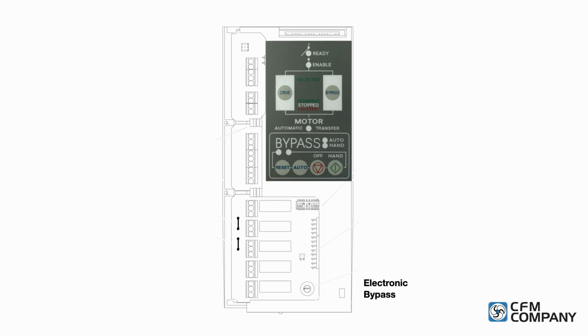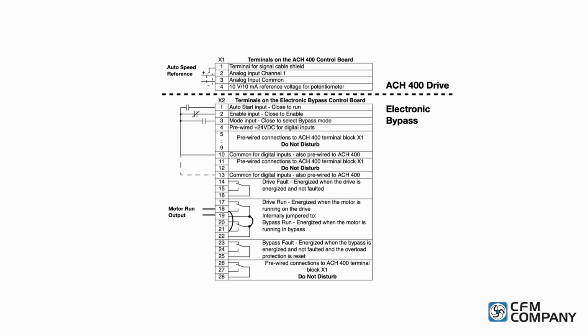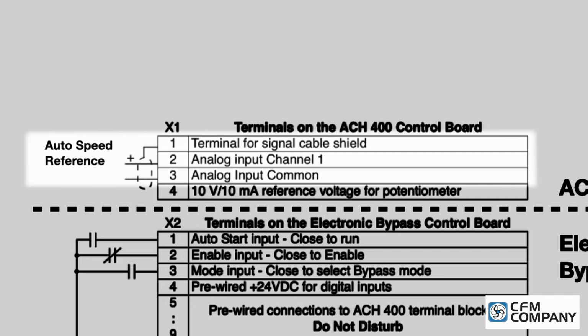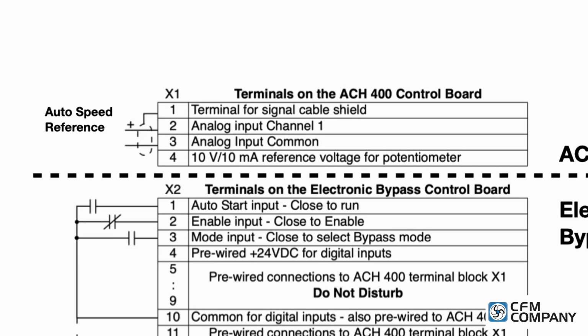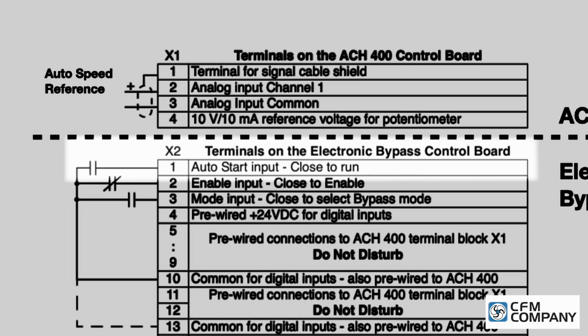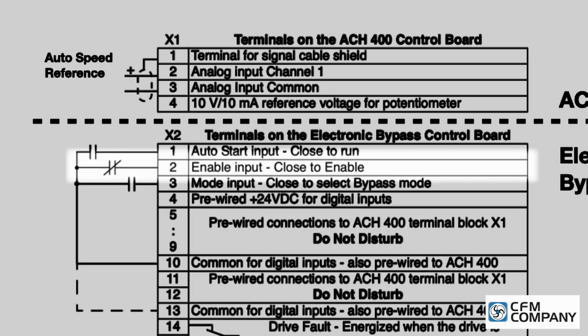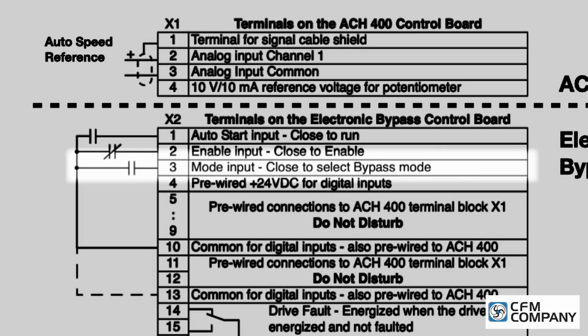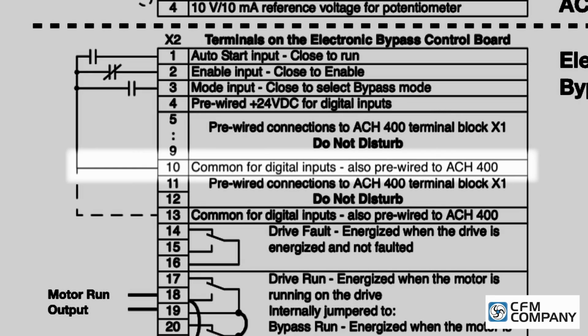Starting with the original electronic bypass control board, EBP, the frequency reference is landed on analog input 1 terminal on the drive. On the bypass, terminal 1 is the auto start-stop command. Terminal 2 is the run-enable interlock used for external safety devices wired in series. Terminal 3 forces the bypass to be active. Terminal 10 is the common reference for the bypass digital inputs.